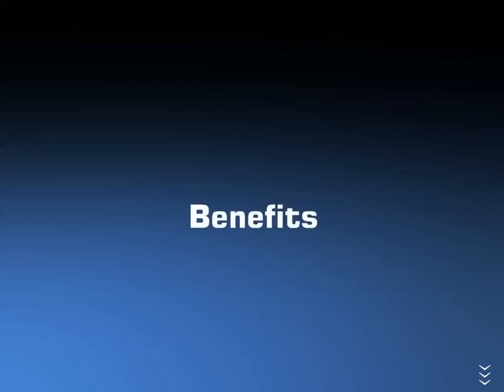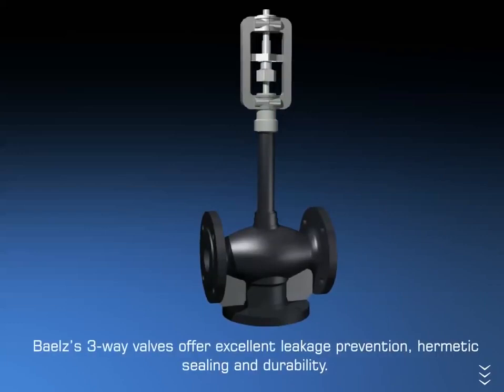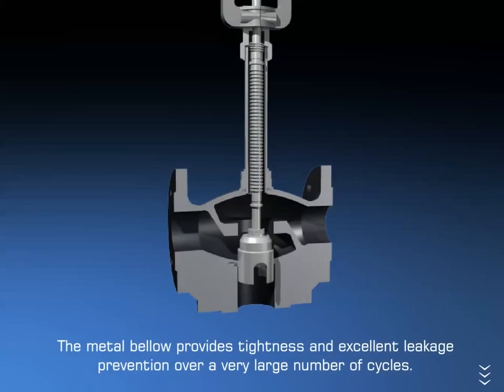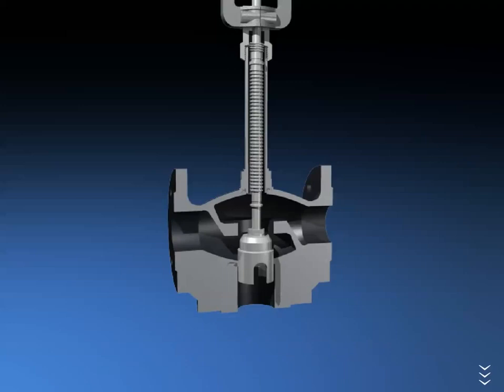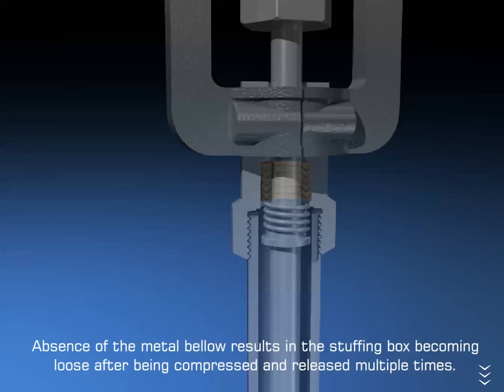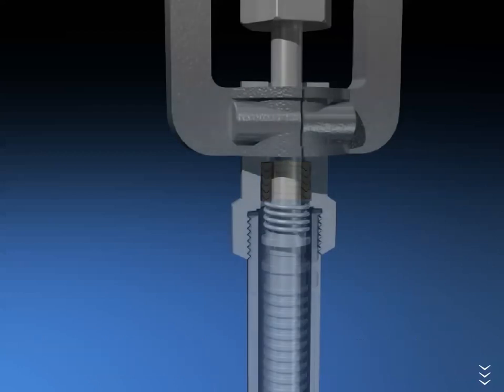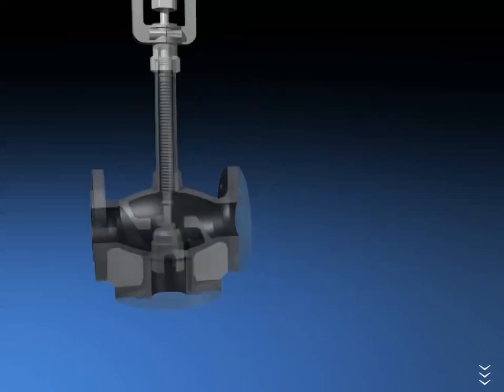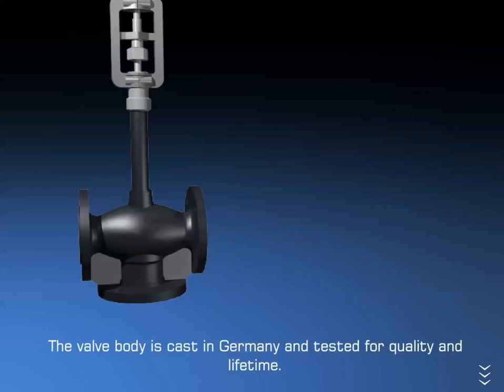Baelz's three-way valves offer excellent leakage prevention, hermetic sealing, and durability. The metal bellow provides tightness and excellent leakage prevention over a very large number of cycles. Absence of the metal bellow results in the stuffing box becoming loose after being compressed and released multiple times. The plug-and-seat design with its molded-in stainless steel seat and needle-line contact areas results in effective, long-lasting, tight sealing. The valve body is cast in Germany and tested for quality and lifetime.